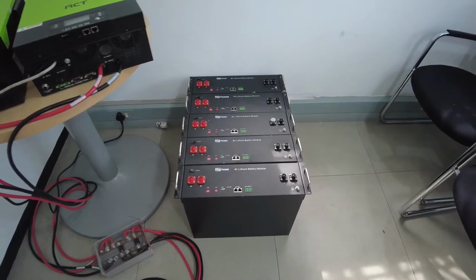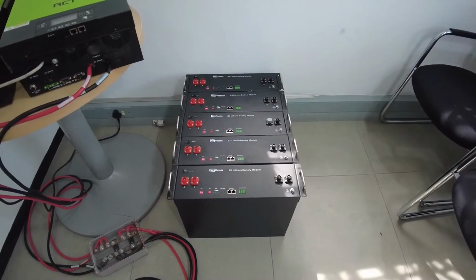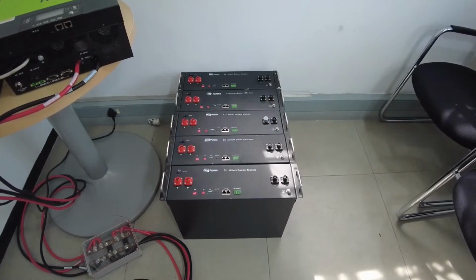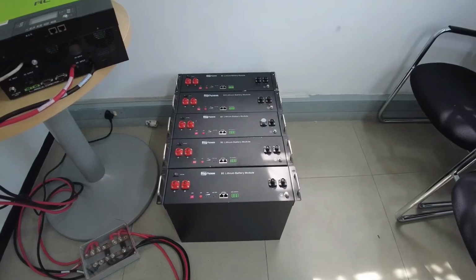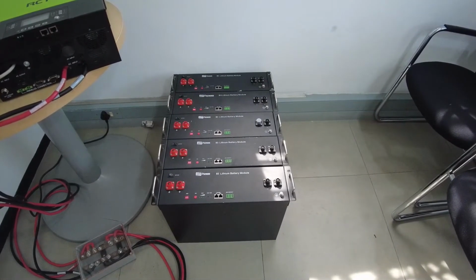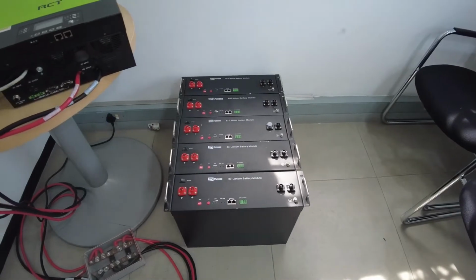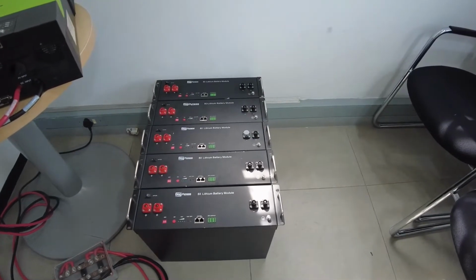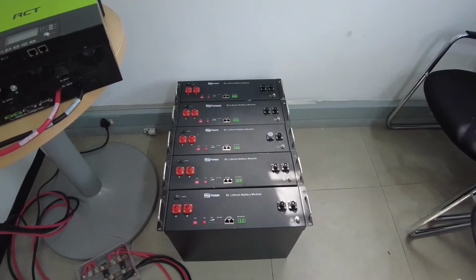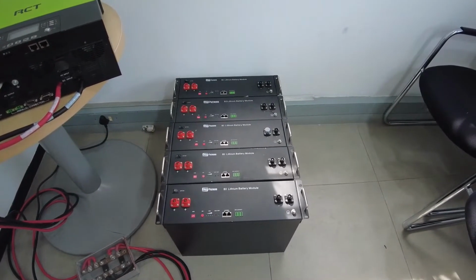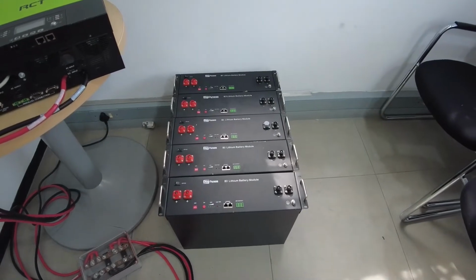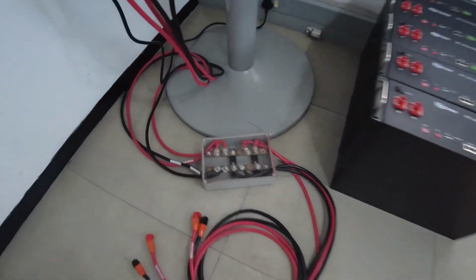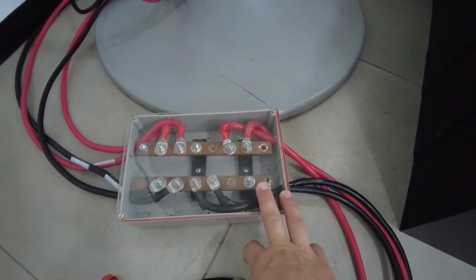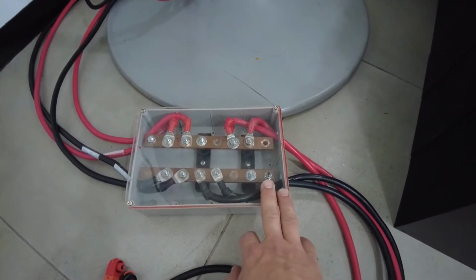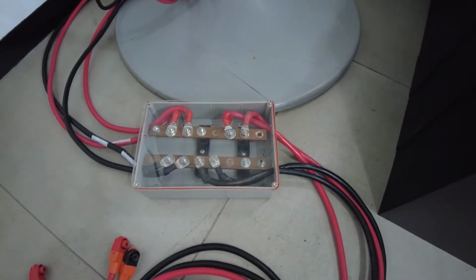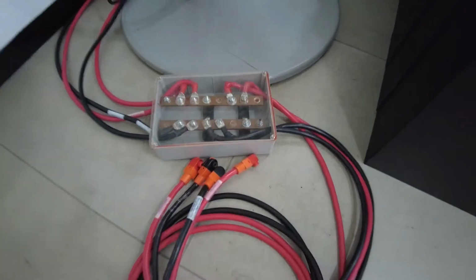Okay, starting with the battery modules. In this case I have 5 B3 modules. Each module rates at 75 amp hour, over 48 volts. If you have a look at 3 of these modules, 3 of them combined will bring you to an amp hour rating of 225 amp hour. So again, you will see that these cables run to your combiner box to evenly spread the load over the cables, so that obviously not one pair of cables handles the majority of the power.